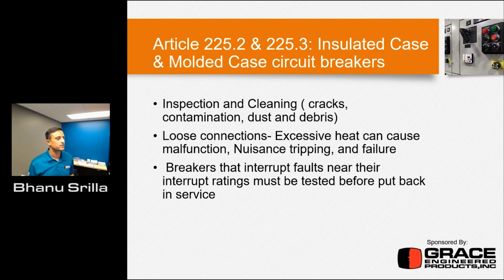You need to make sure they're inspected and cleaned, and verify there are no visual cracks or contamination, dust and debris. Contamination is one of the important things I would like to emphasize here, because in the industrial setting you see a lot of contaminants on these breakers, right? Which will lead to ventilation problems, and which will in turn result in temperature rises. When the temperature rises, the contacts go bad or the equipment goes down, right? So just make sure that you monitor those breakers. Loose connections and excessive heat can cause a malfunction, nuisance tripping, and failure as well. And also, whenever you're trying to look at the breakers, right?